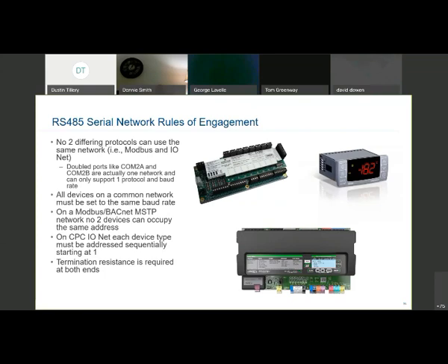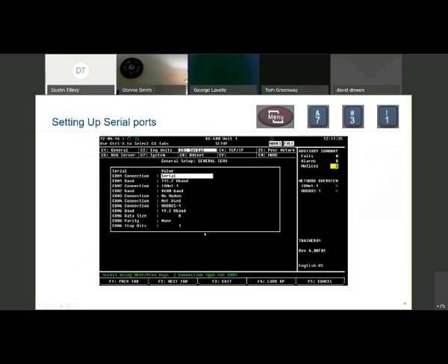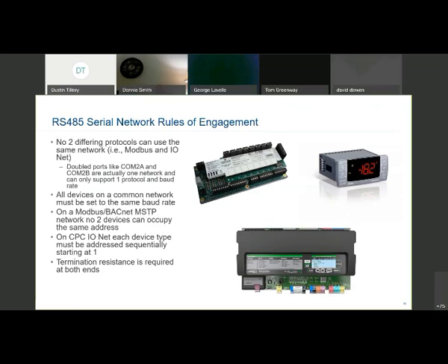On the Modbus BACnet MSTP, no device can occupy the same address. Whereas if you had one of these devices that was BACnet or Modbus and another device, you cannot have them both addressed as number 1. One item would have to be number 1, the other number 2, 3, 4, 5, so on and so forth. Now, with the addressing on the Modbus, you do not have to go sequentially. So you could have one device addressed as number 1, another device addressed as number 3. You do not have to have another device addressed as number 2. However, with the CPC I/O Net, each device must be addressed sequentially starting with 1. So therefore, we can't skip numbers. We have to go 1, 2, 3, 4, 5, so on and so forth on down the line.